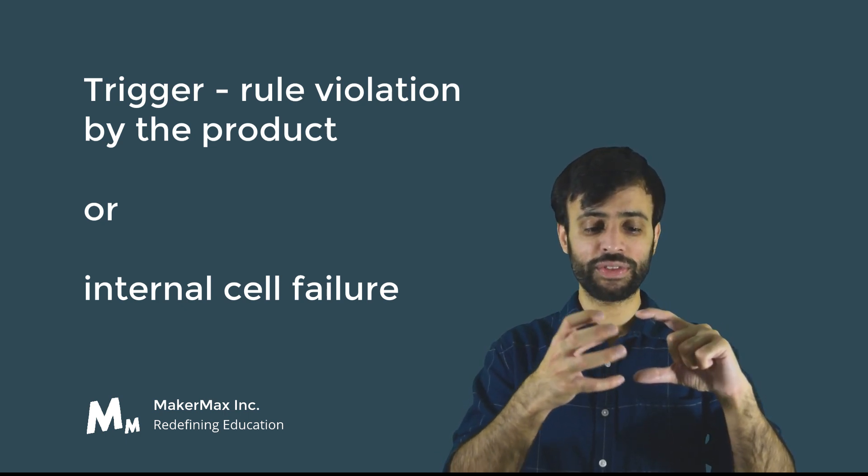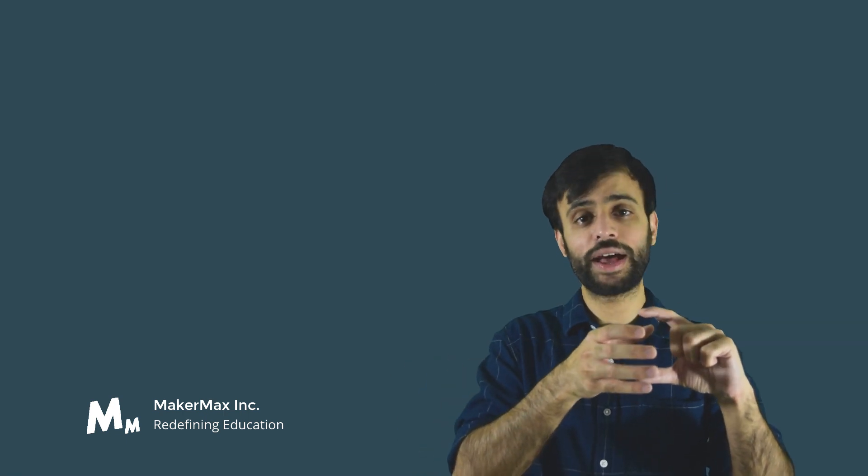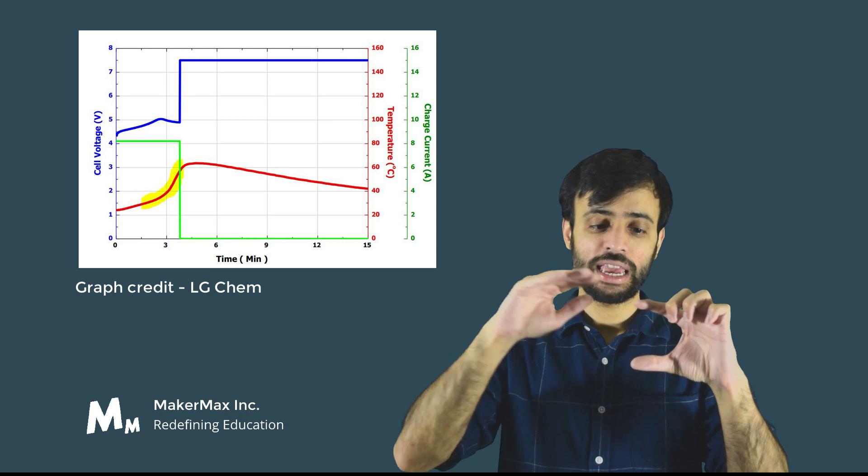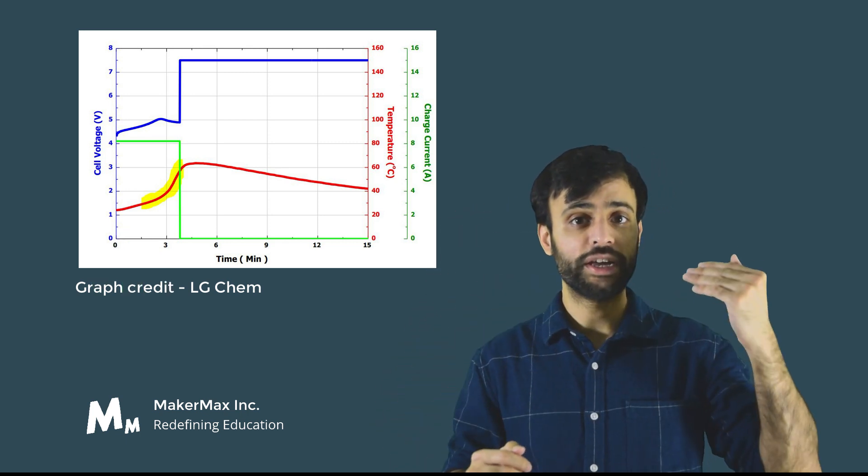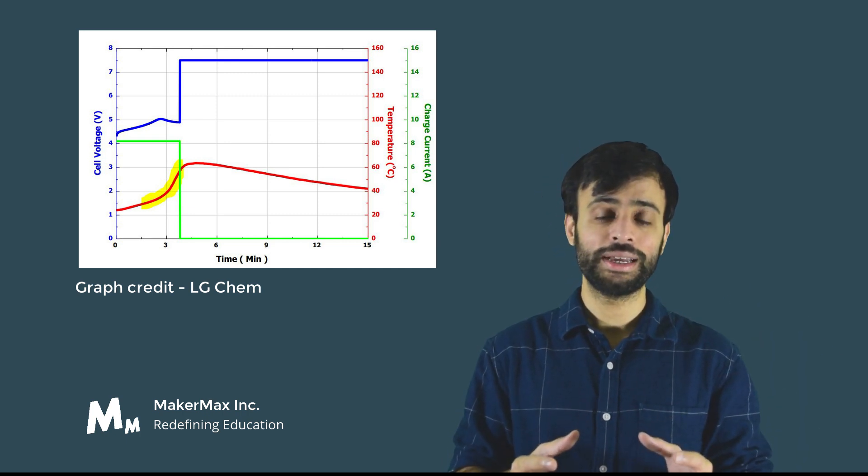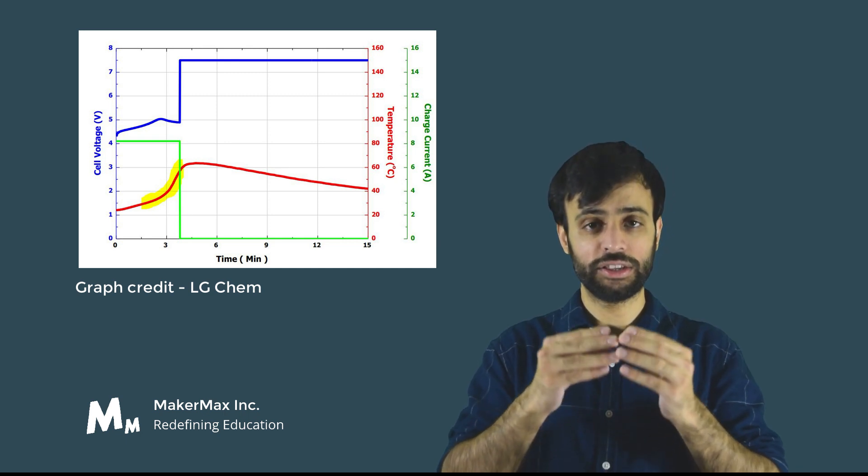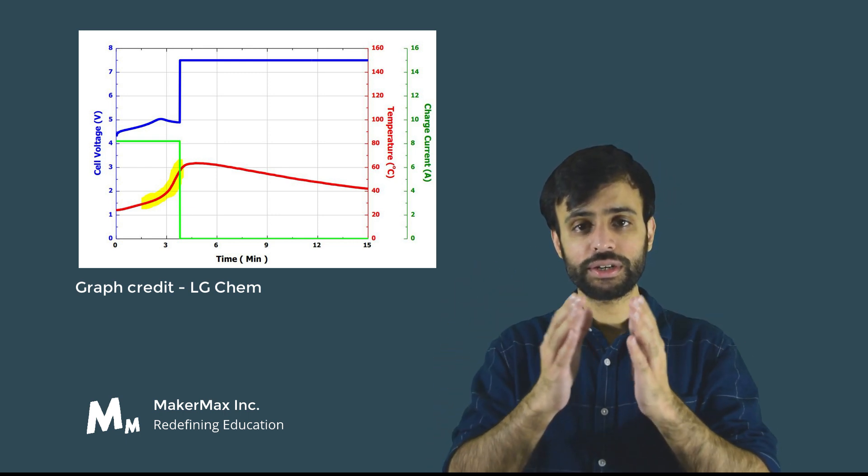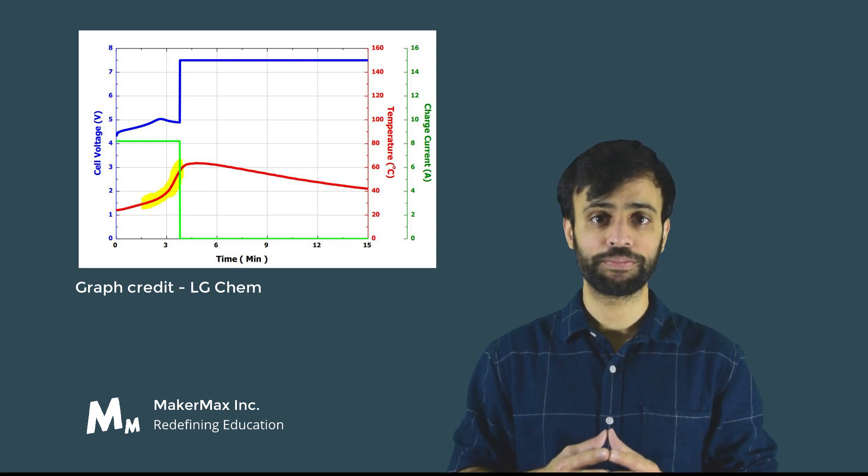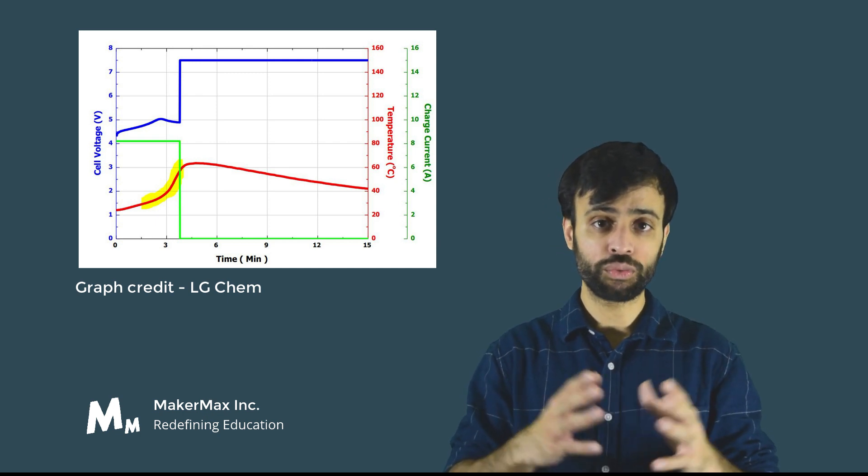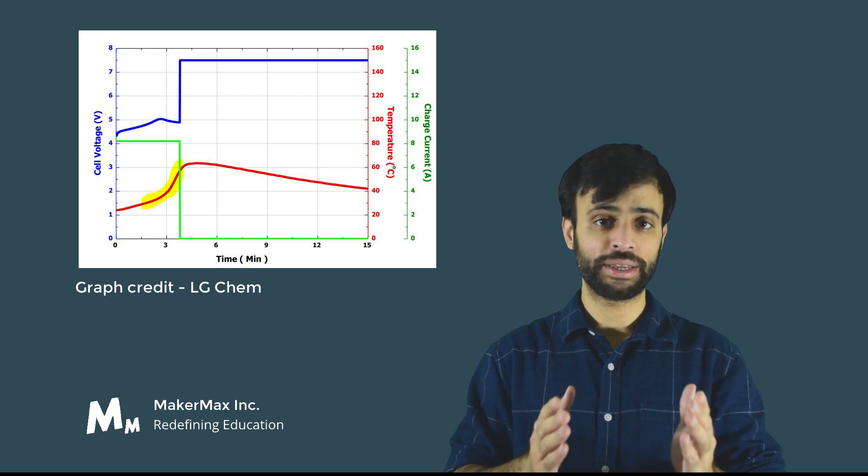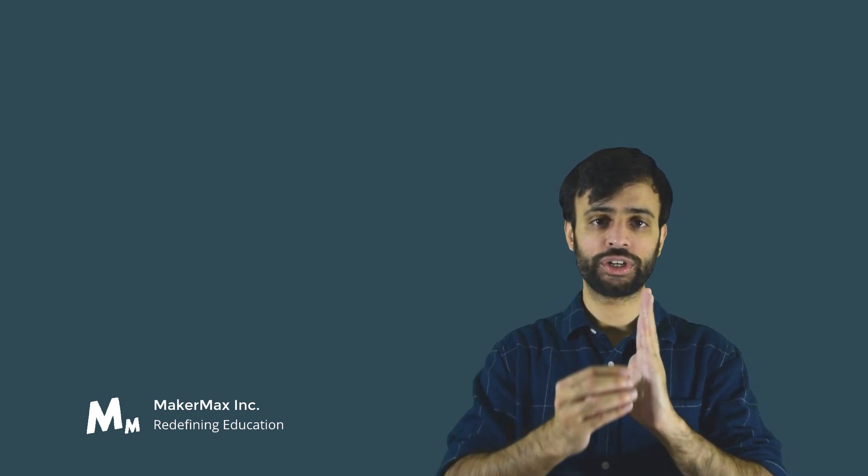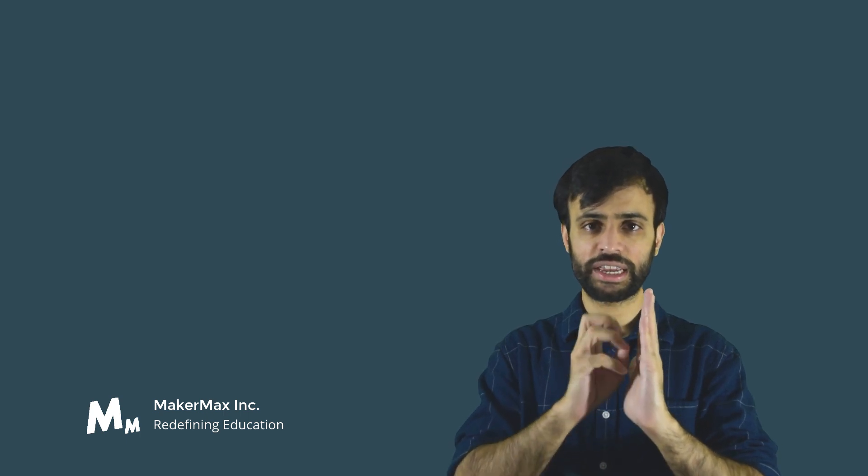Because of that heat being generated, if that heat cannot be removed as fast as it's being generated, then the temperature of that cell will rise. When the temperature rises beyond a certain point, that's when we start initiating stage one of thermal runaway. In stage one, certain reactions start happening inside the lithium-ion cell—the lithium starts combining with the electrolyte, and the electrolyte slowly starts vaporizing. These reactions are catalyzed by that higher temperature, which was caused by violating one of the rules governing the cell.